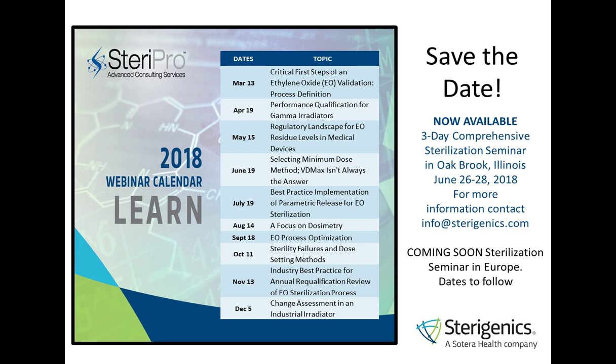So it's always a good idea, and the standard actually supports this as well, that you place internal PCDs or BIs throughout the load. The reason you do that is because you want to make sure you're challenging every part of that load. It's important to make sure that that BI is placed in one of the most challenging locations, but by placing it throughout, if there's a cold spot in the chamber, you're going to capture that. So you want to make sure that you characterize the entire load and place them throughout the load.